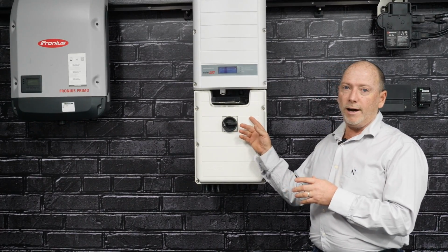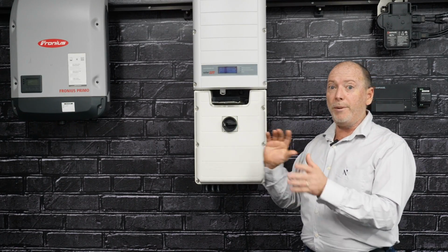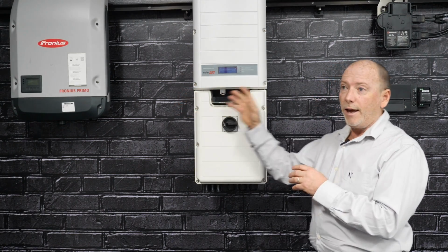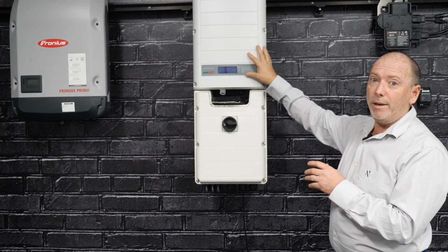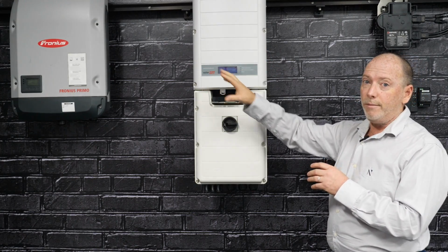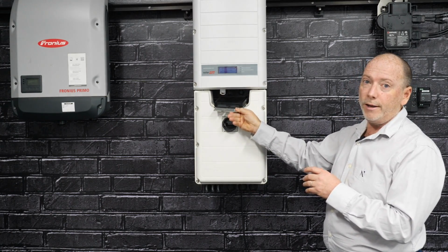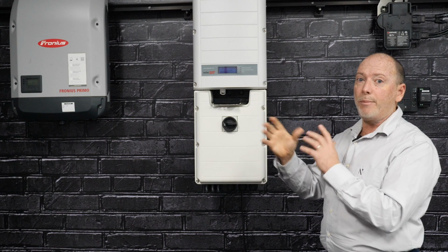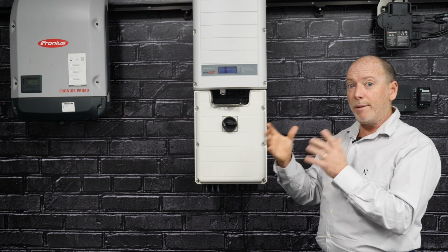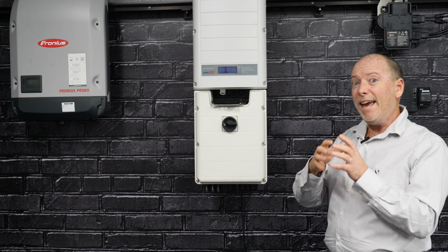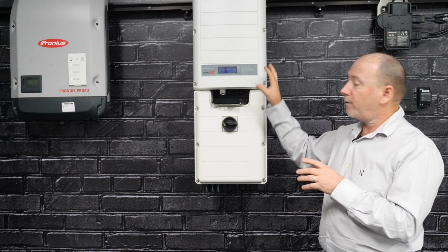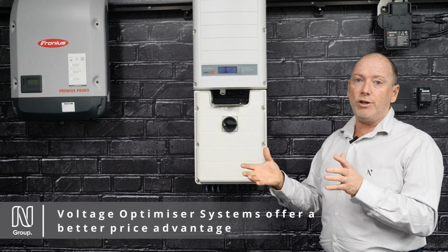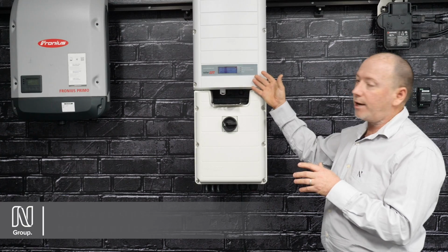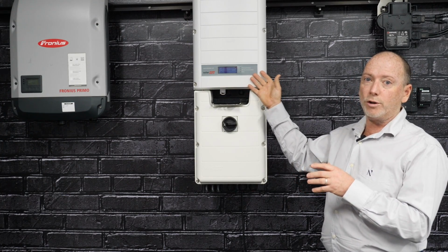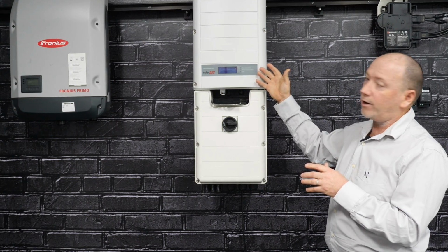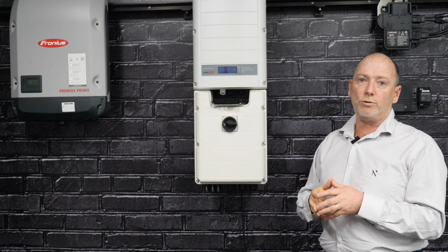The system here in the middle is called a voltage optimizer system, a mix between a string system and microinverters. In short, we still have a big box on the wall like with a string system, and a small box that goes behind each panel which separates things out. We get some of the benefits of a microinverter system, where each panel operates individually, but we still have a big box on the wall and still have high voltage DC. We find this has a price point advantage, especially in the commercial arena, and most of our Solar Edge installs have been on larger commercial sites.